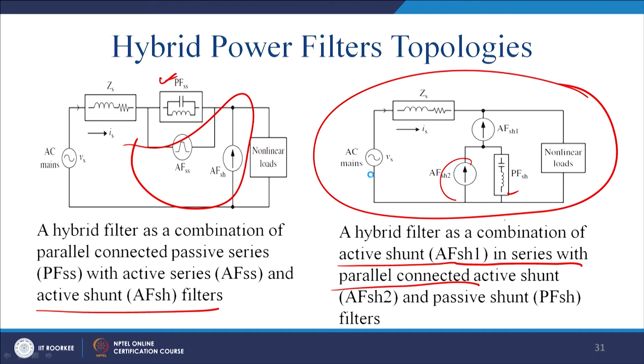It is a retrofitting - you are using, first you had this, it is a history of conversion. First it may be that a capacitor was only placed to mitigate the power factor problem. Once you see the power factor problem, and if you have an adjustable speed drive, it causes a problem. So you cannot leave this capacitor alone, and for this reason you put an inductor. So that inductor essentially gets a selectivity, this LC combination, a single tuned filter. Once you get a single tuned filter, you find it is not enough to compensate because of the detuning problem, and the aging problem, and thus you place a UPQC.